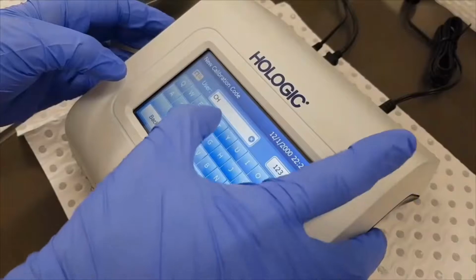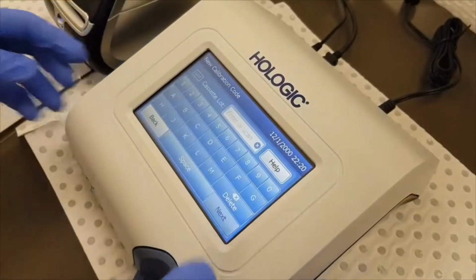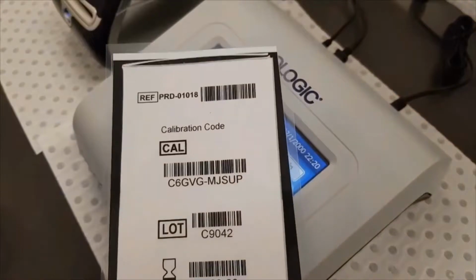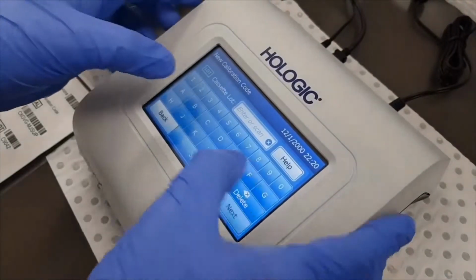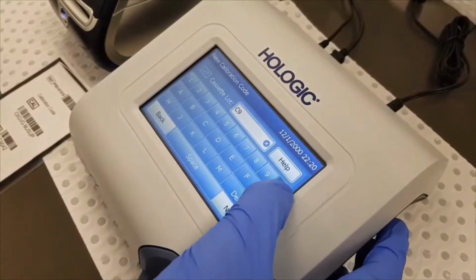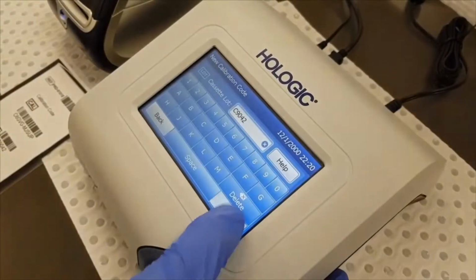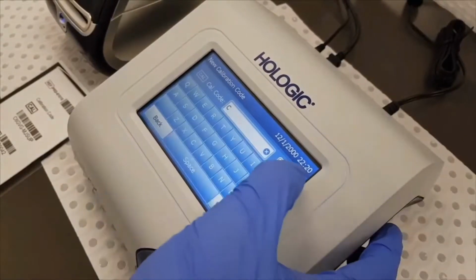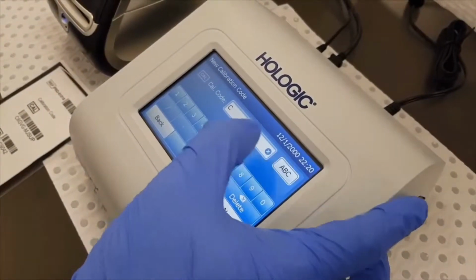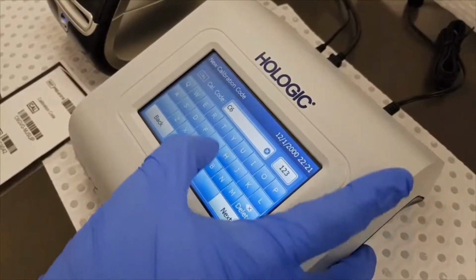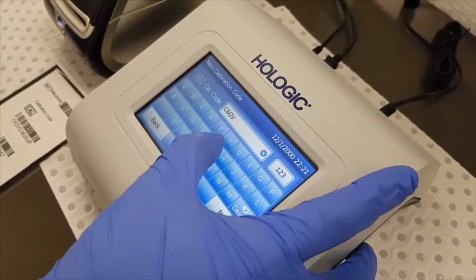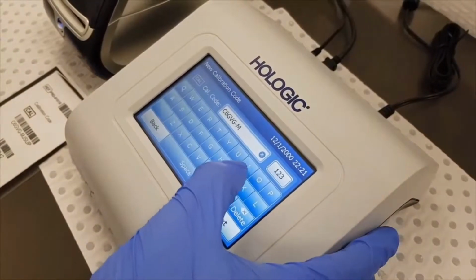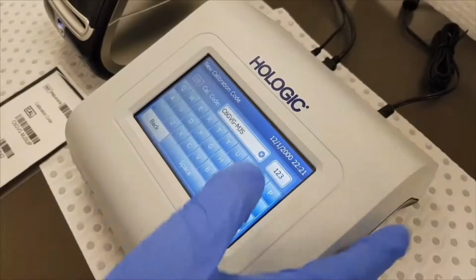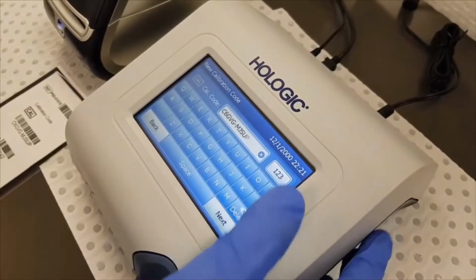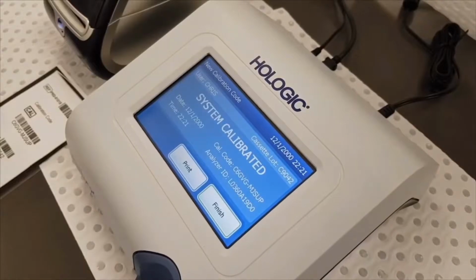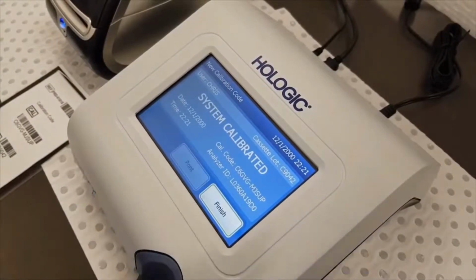Next is calibration. Enter your user ID and click Next to enter the cassette lot. This is found on the insert provided or in the packet of the cassette you will be using. Carefully enter the calibration code. This is also found on the same insert. It is important to program this code correctly to prevent an invalid result from occurring. Once the system is calibrated, you may print the results and finish to proceed to the next step.